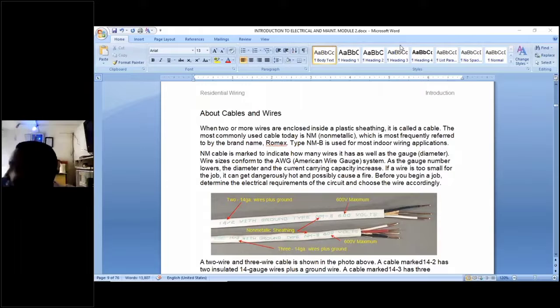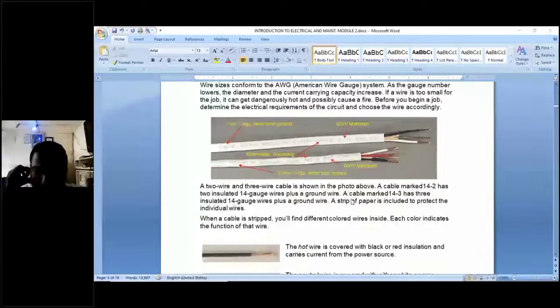As the gauge number lowers, the diameter and the current carrying capacity increase. And if the wire is too small for the job, it can get dangerously hot and possibly burn and cause a fire. So before you begin a job, determine the electrical requirements of the circuit and choose the wire accordingly. A two-wire and three-wire cable is shown in the photo above. A cable marked 14-3 has three insulated 14 gauge wires plus a ground wire.